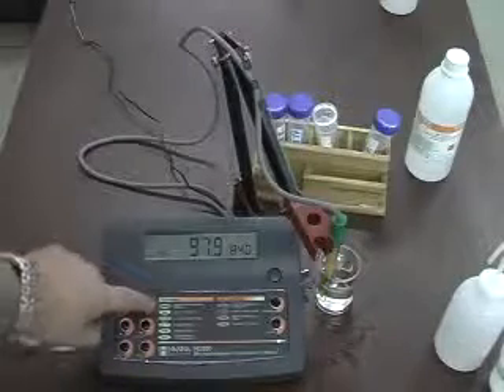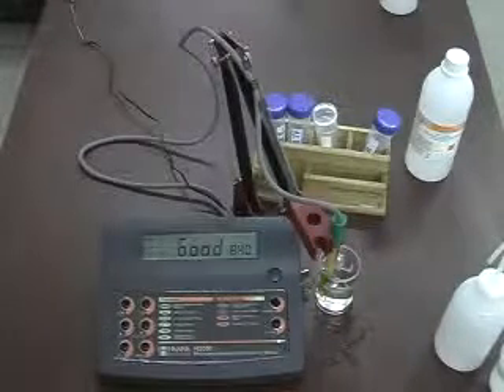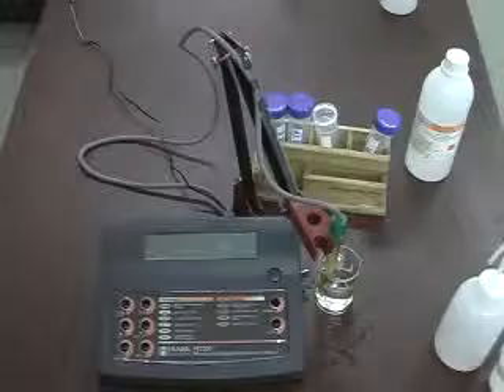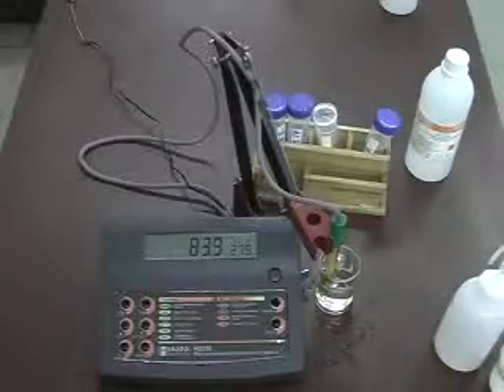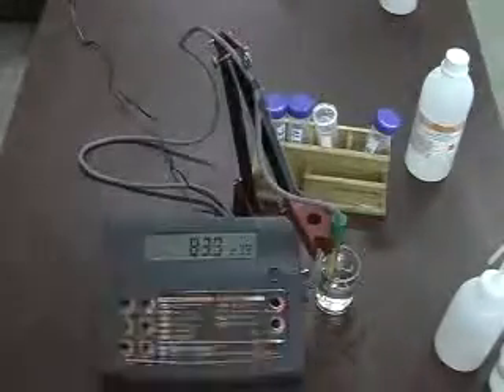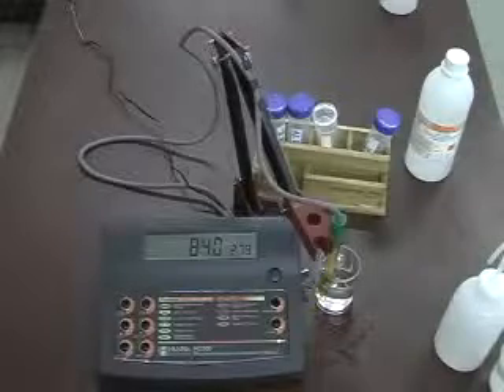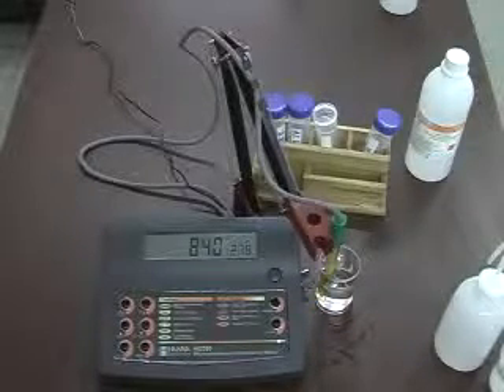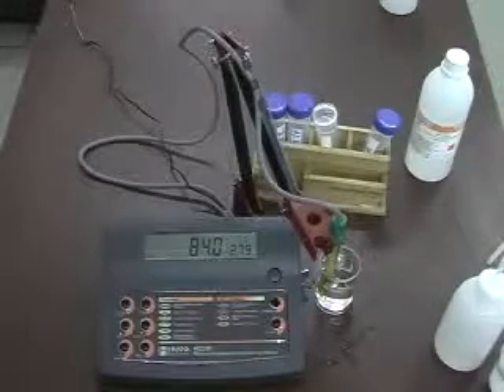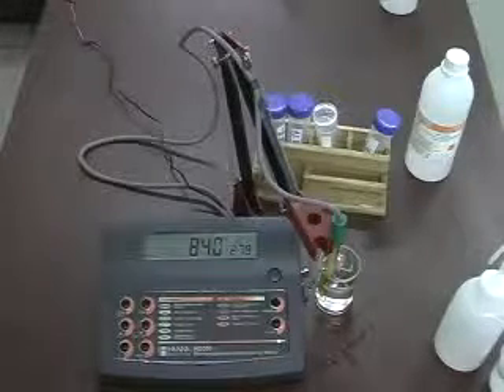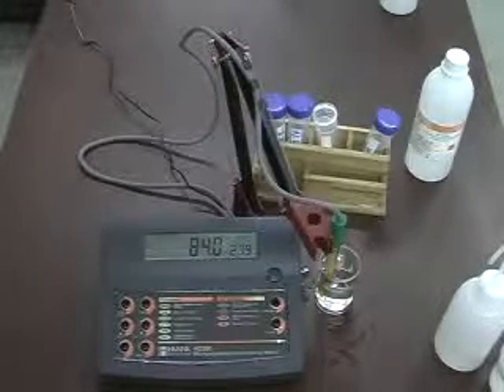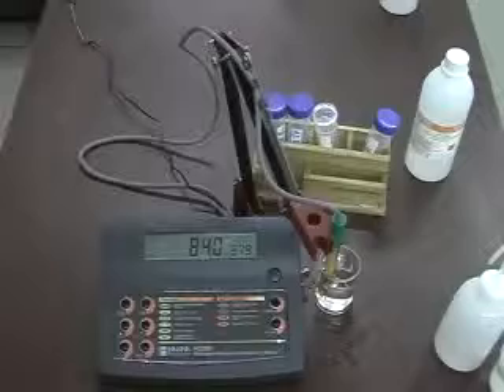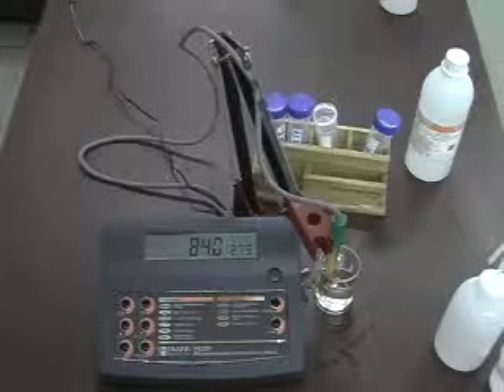Again, I will press the confirm button, and now I just told it that it's 84 microsiemens, and there is a chance that that is not truly 84 microsiemens just by the contamination within the probes, but it is going to be relatively very close. This shows again the basic calibration procedure for our HI 2300 auto ranging conductivity meter.